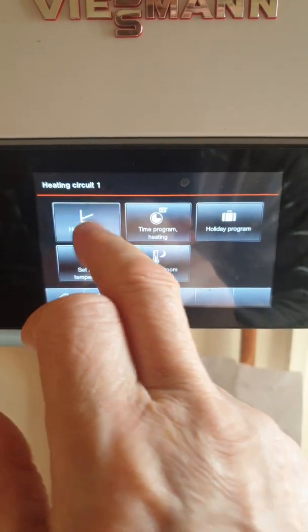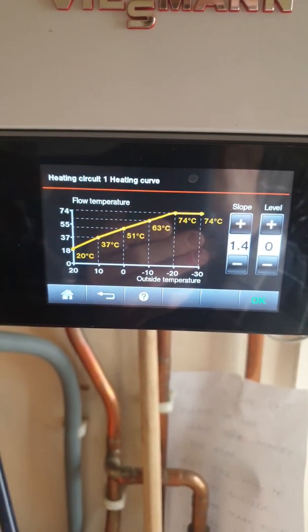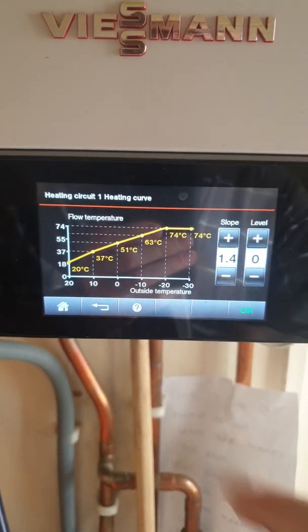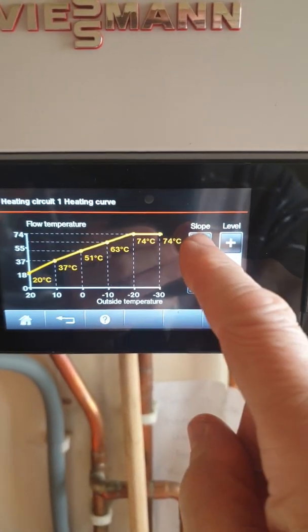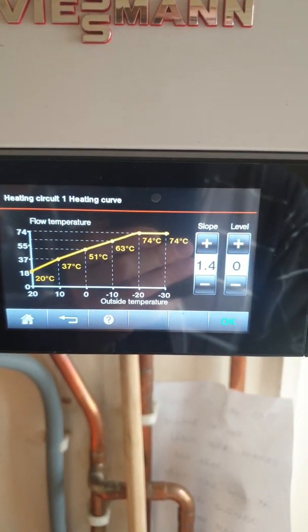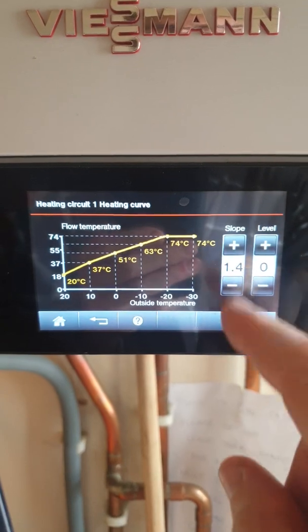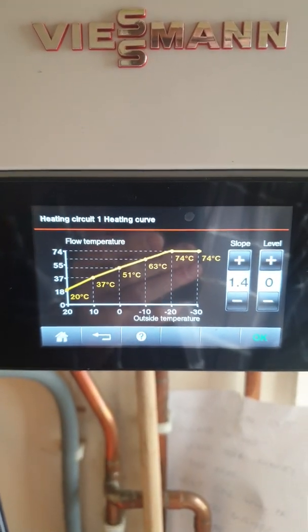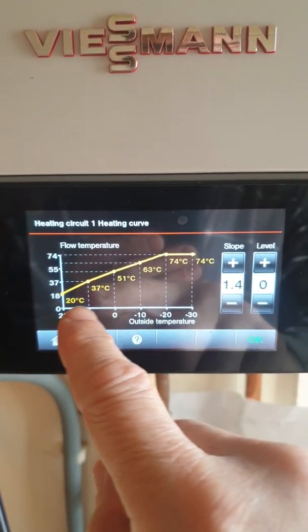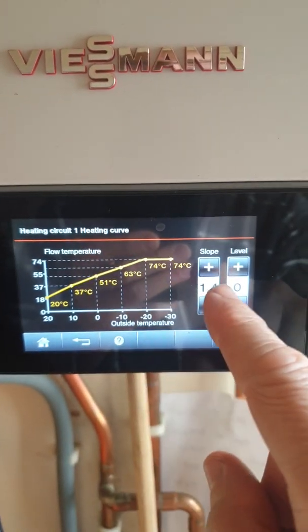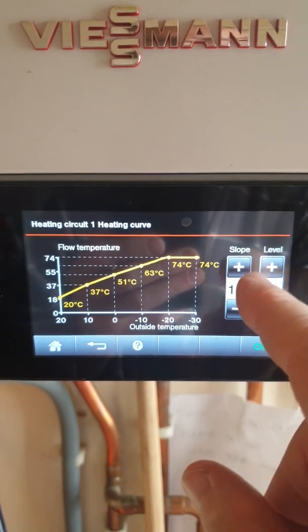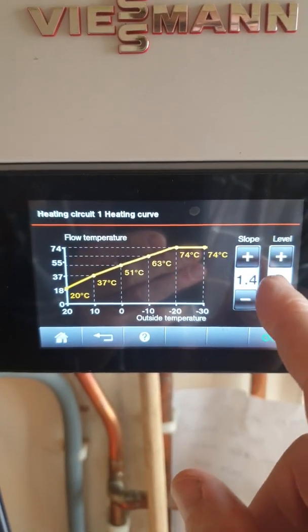So if we go into my boiler — this is my boiler in my home — heating curve. This is actually the third take I've done of this video and I've learned a few things myself from coming to explain it. We keep referring to 'curve,' but on the boiler it says 'level' and 'slope,' and then we've got something called 'parallel shift.' What I've realized is if you have an amalgamation of slope and level, that would then be your curve. The level is actually the parallel shift, so I think they are the same. Slope and curve are not the same because it could be an amalgamation of the two.